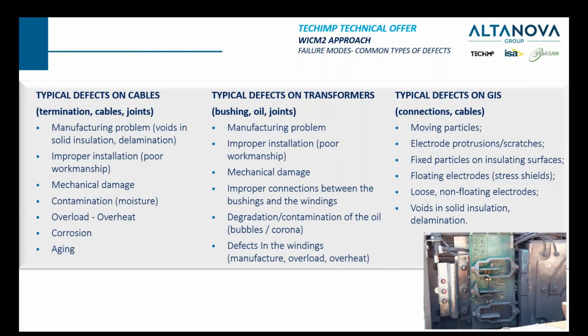The common faults for typical apparatus like the cable, transformer, and the GIS or switchgears are listed here. I think those are sort of common problems. I will not read all of them, but basically it includes manufacturing or installation problems, and over 50% of the failures are caused by those two reasons. And there are some other reasons such as mechanical damage, overloading, or corrosion, and of course aging or degradation. Those are also the causes of faults.